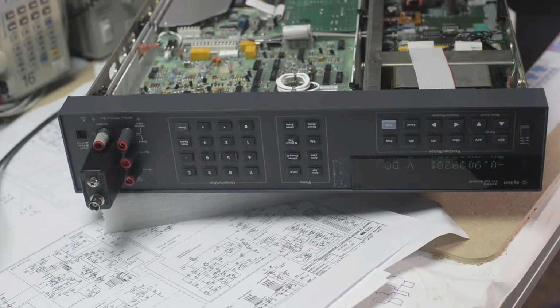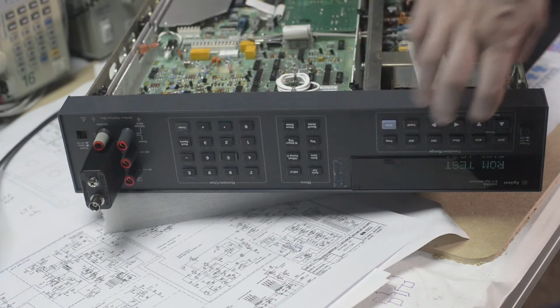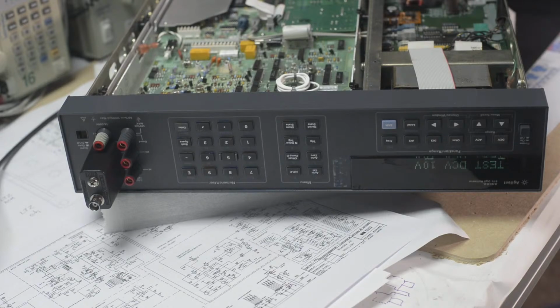Okay, let's run the self-test. So the beginning is good. Usually the self-test procedure runs DC ranges first, then switches to, if I remember right, resistance, current, and then AC. So I expect the meter would run for some time, and then it will fail. Normally self-test is pretty quick, takes about 140 seconds. And there is the AC test. Ratio is okay. AC DC 10 millivolts, 100 millivolts, 1 volt, 10 volts.